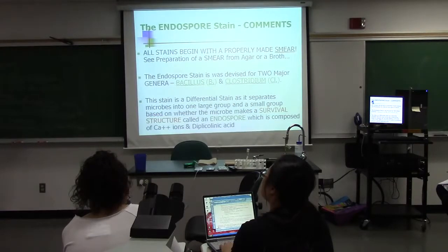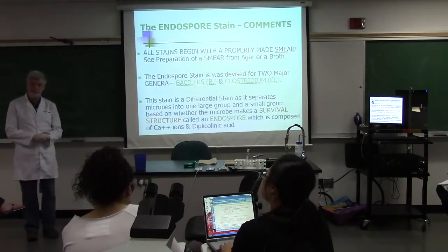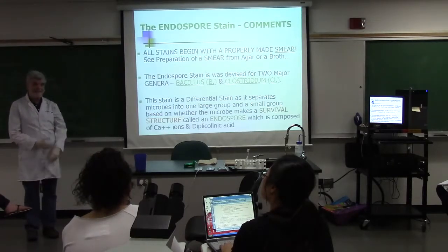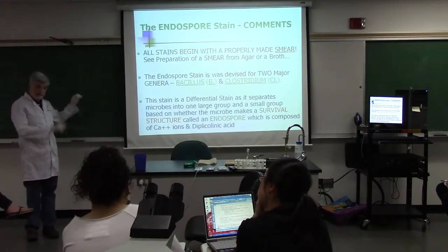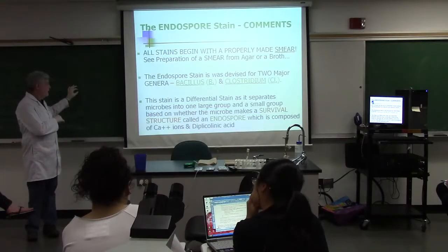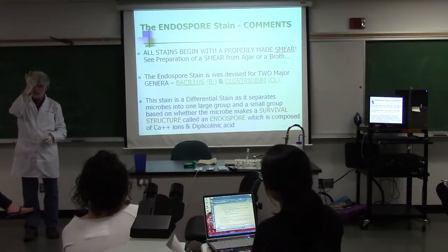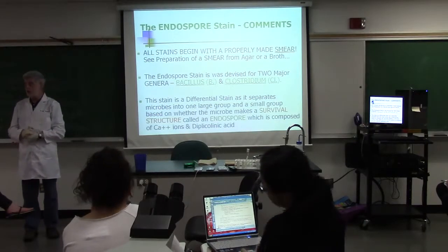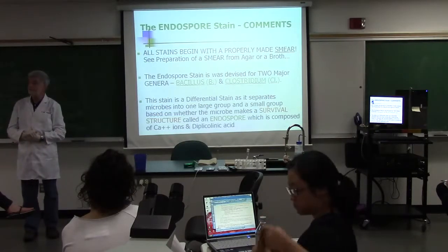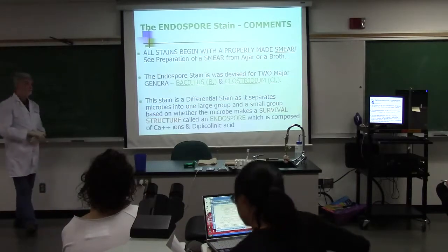And we actually test our autoclaves with it. Once a month, if you're in a hospital environment, you're supposed to run an autoclave test where you buy a little strip with this bacteria's endospores on it, and you autoclave it, and then you drop it into sterile broth and stick it in the incubator, and if it turns cloudy, your autoclave isn't working. So this is how we make sure that our sterilization process is working on the autoclave.